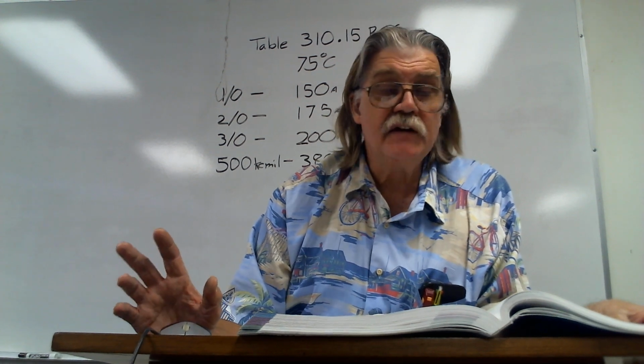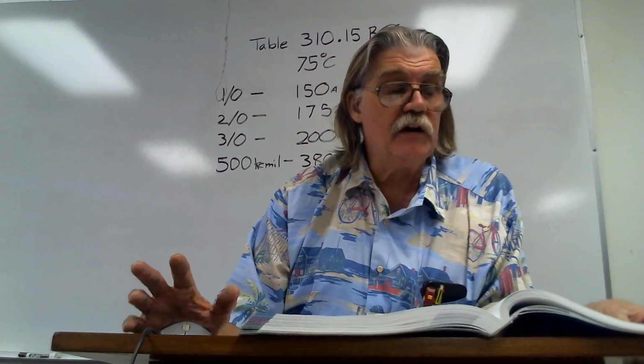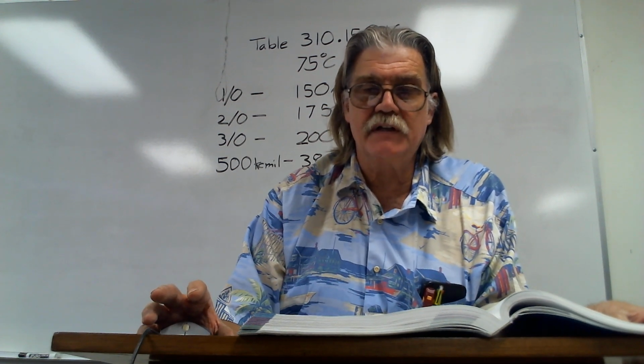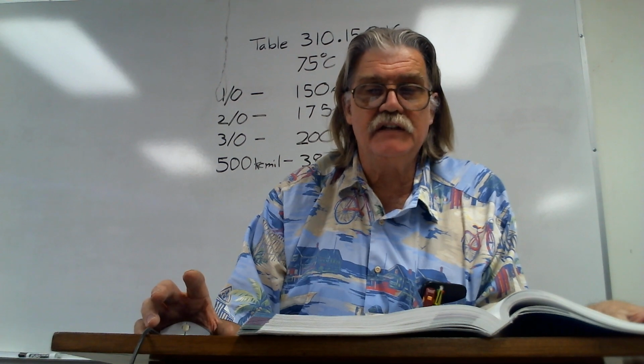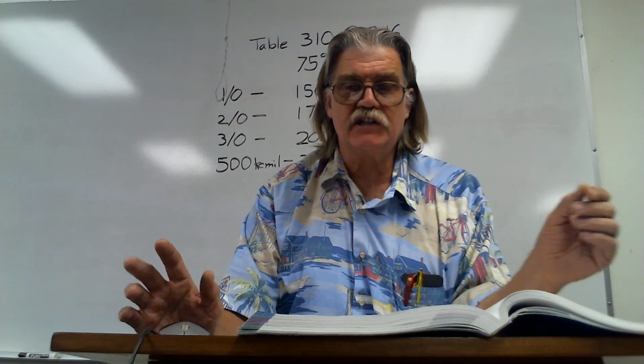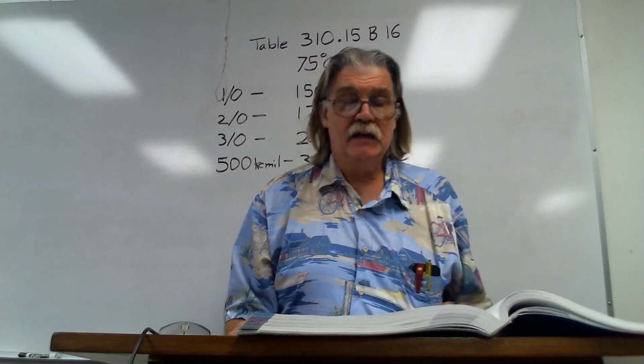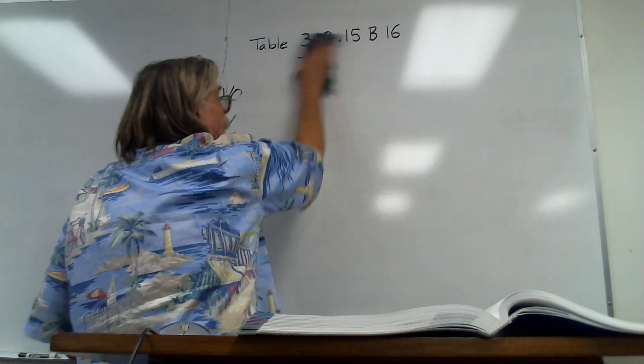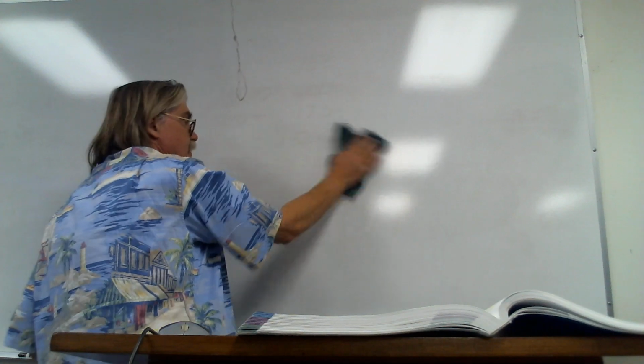Okay, and then we're going to now look down, and we want to know what size for the breaker, and we just read we could use 225%. If you guys want to think of the easiest way to calculate percentage, think money. Let me show you what I mean real quick, okay? Let me just erase this really fast. Sorry, my back is to you. Okay, got that erased, and we're going to write it up here.